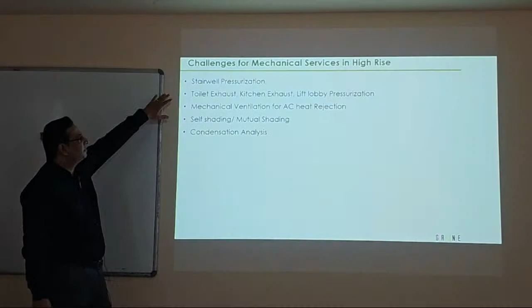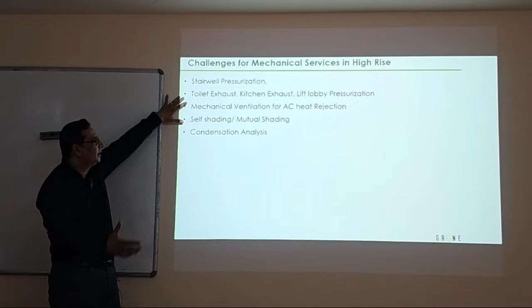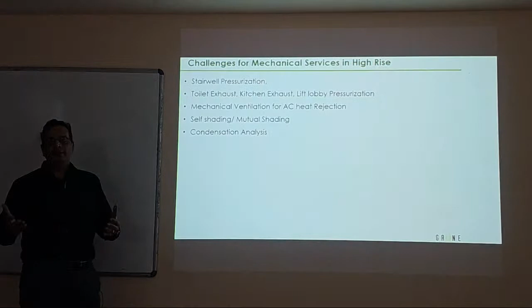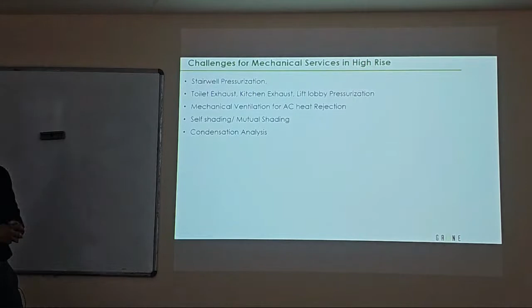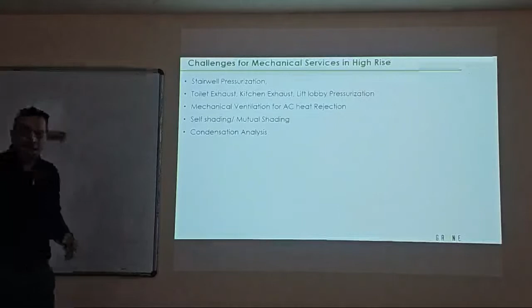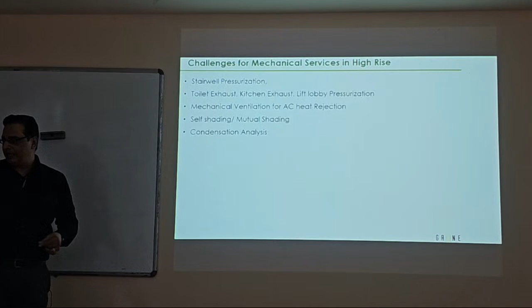You have several staircases to be pressurized. You have toilet extraction to be done, kitchen exhaust to be done, mechanical ventilation, heat rejection. You also look at shading of the building. And in projects closer to the sea, the condensation on the property becomes a very critical analysis. Suddenly you do a big glass building and you're not able to see outside because it's all condensed. That's where your visibility from in to out is also changed. So it's very important to design how much your window wall ratio should be when you're doing this kind of building. Just a little pointers to think.